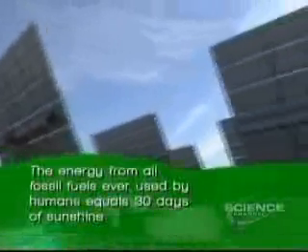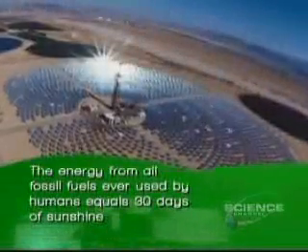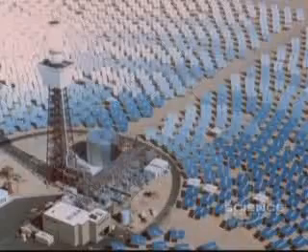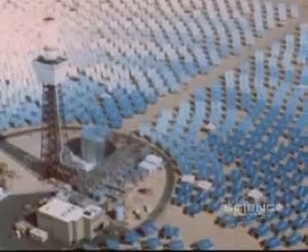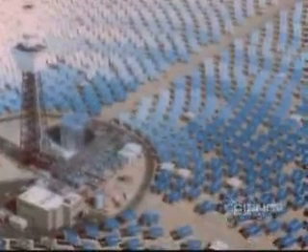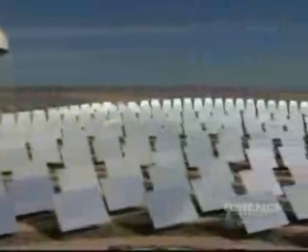Those heliostats can fail. They've done it before at a different tower, Solar One, in Barstow, California. Behind the mirrors in the California plant, engineers had used concave foam pads to help focus the sunlight and to absorb shocks from storms. But moisture collected between the foam and the metal casing. The mirrors corroded and lost their efficiency. In the end, the plant's energy was considered too expensive.